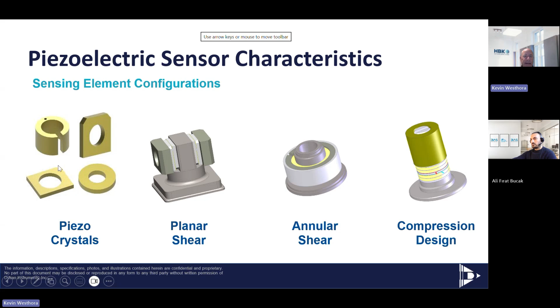On the left is what's happening when we're at rest. So we have two crystals in between an insulator. And at rest, we align the crystals so that their polarity is neutral. So the plus and minus align to give us a neutral output at rest. And then as we start to vibrate or shake the accelerometer, we start to get a deformation and we start to shear the face of that crystal. And we start aligning the sensitivity so that we get a plus in the up direction and a negative in the down direction. All right, so that's kind of what's happening when you're shaking an accelerometer. This deformation that you see right here is actually in the angstroms. The naked eye can't actually see that deformation.